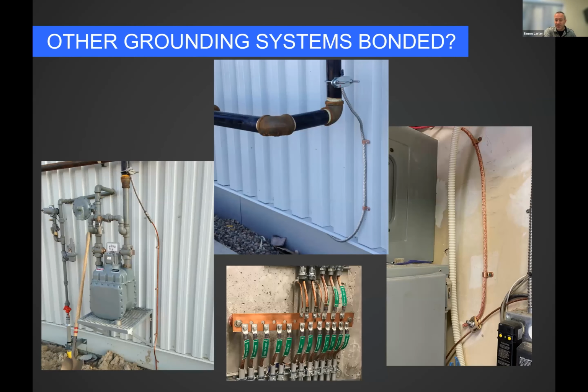Are the other grounded systems bonded? You'll have to double check that. The only time this might look different is if you have a gas distribution system that has a cathodic protection current run on it, then they do not want us to bond directly to their gas piping. And we always have to bond on the customer side of the meter. We don't want to bond on the other side, mainly because on the other side, sometimes that's where they have the cathodic protection. They're running current, so if we ground it to the supply side of the meter, we'd be draining off their cathodic protection current, and that's going to make a mess of things for the gas company. So they don't like us to do that. Always bond on the customer side.